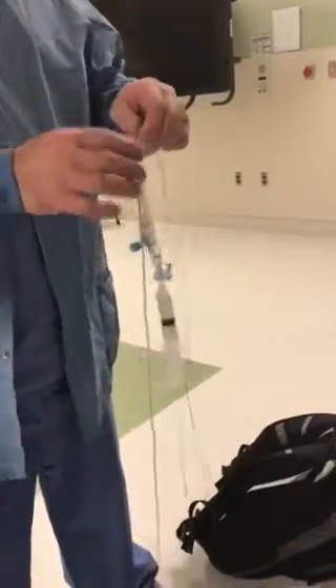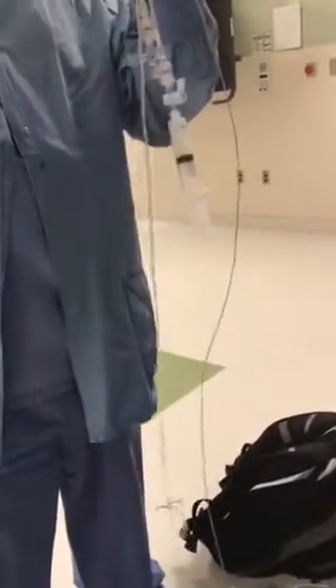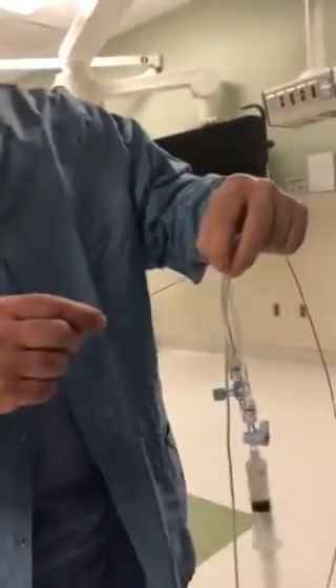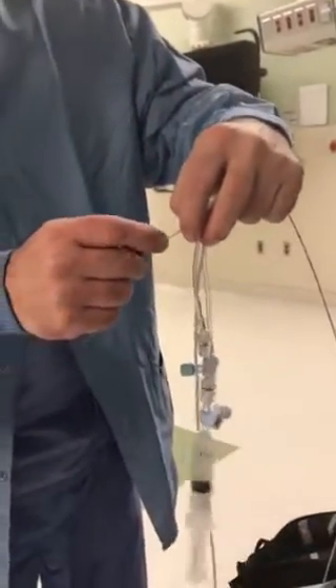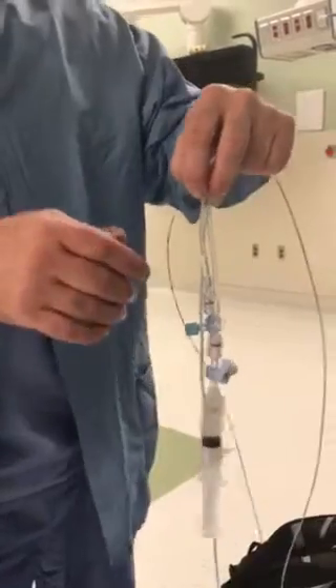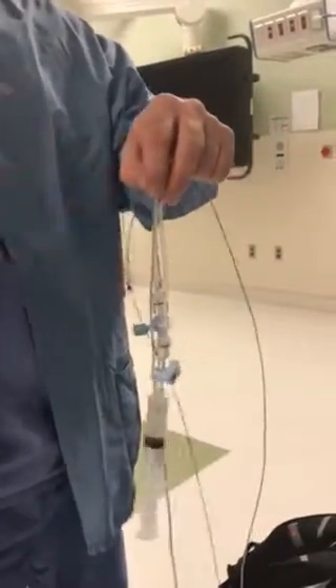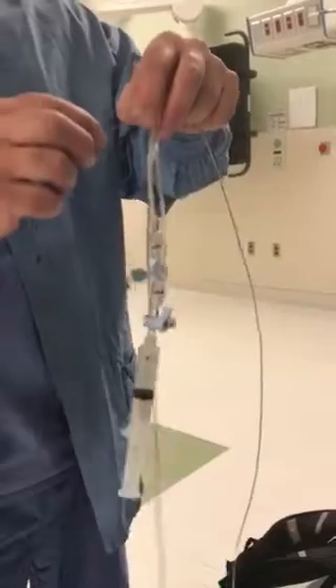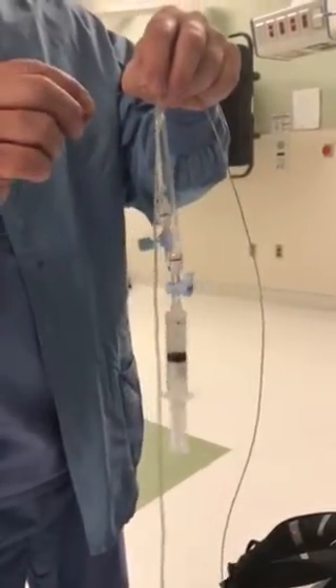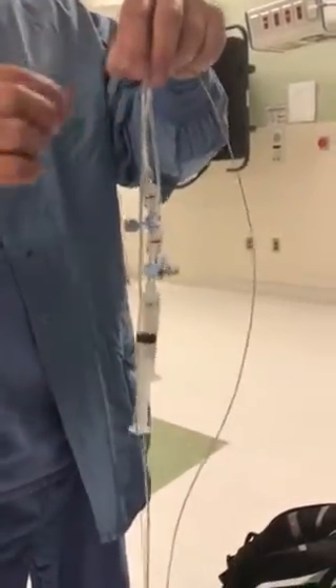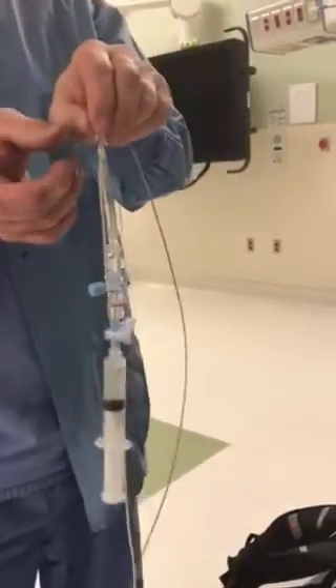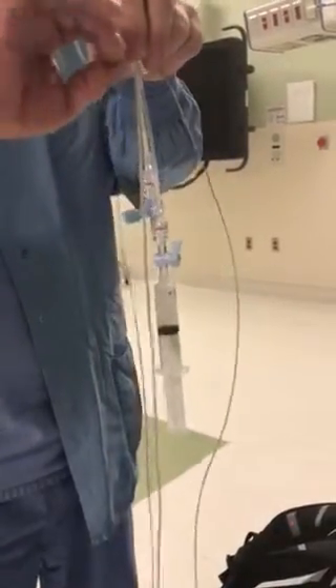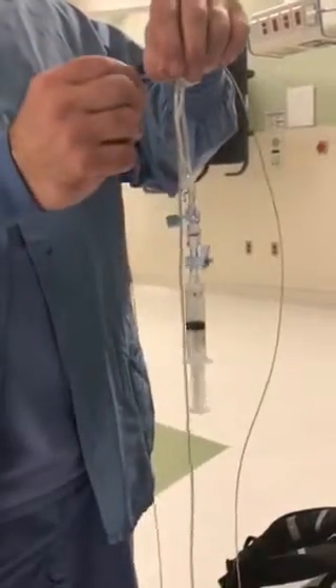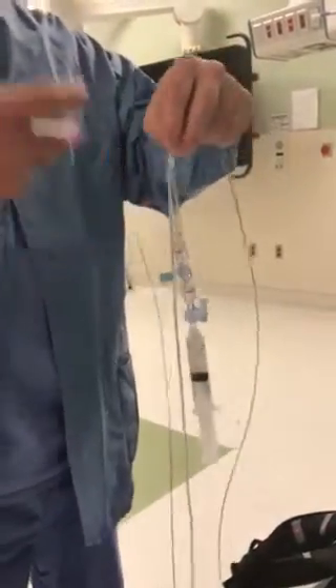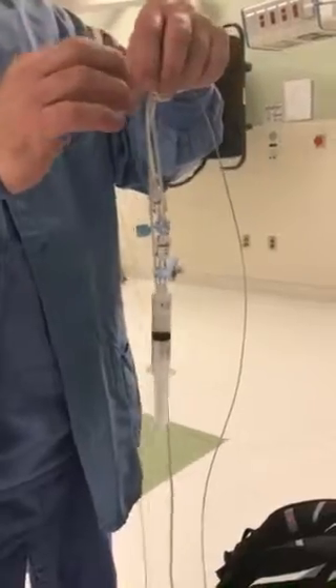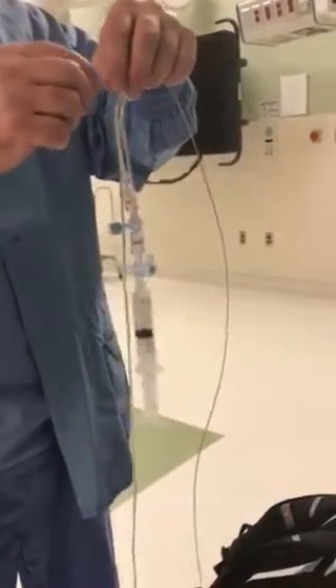Because after a 30 centimeter device, I'll show you too, you can't really see them that well, but each one of these little dots represents part of the ultrasonic transducer. So after a 30 centimeter, which is 1 centimeter apart, a 40 and a 50, a 40 is 1.4 and a 50 is 1.7 centimeters apart. So there's that separation, so it makes the wire a little floppier and may not advance as easily. That's why I have that syringe attached. You feel any resistance, pull back, put the syringe, start flushing, and advance nice and slow.